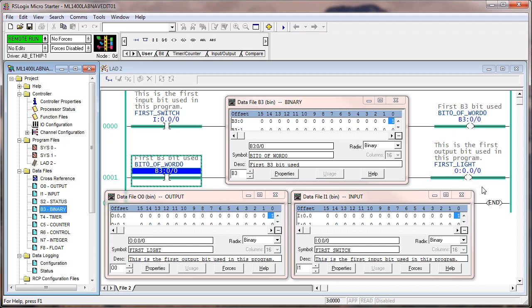What does this tell you? That regardless of the state of what you see on the screen, the mode that it's in is the dominant force at work. If it's in the program mode, you can go in there and flip stuff around to your heart's content. But the moment you put it in the run mode, the actual field device states for the inputs take over and the logic takes over, and you can click and toggle all you want to no avail.